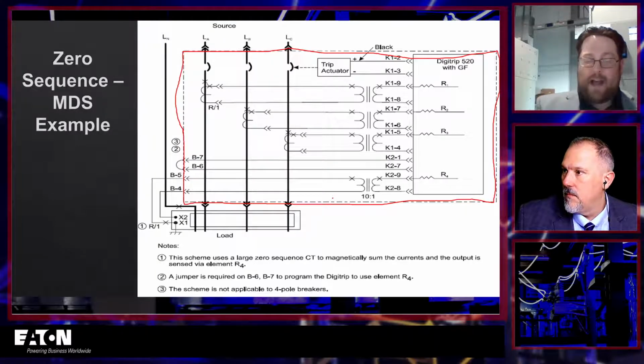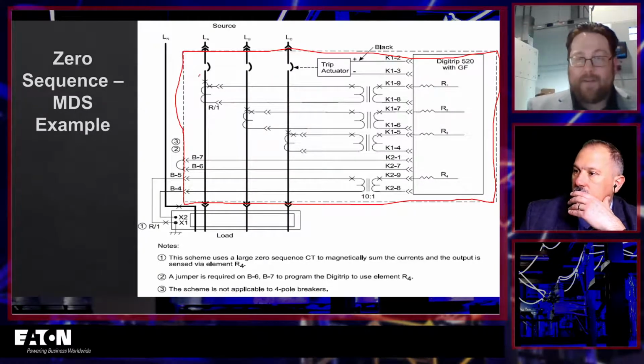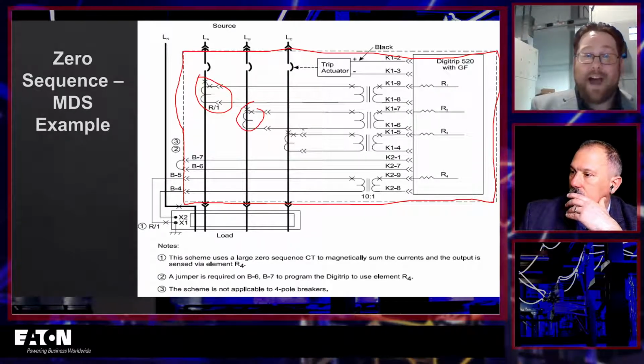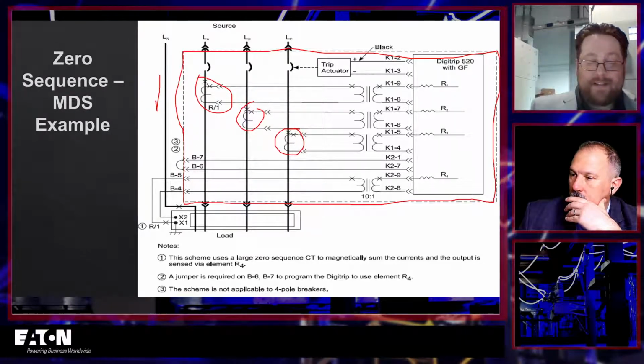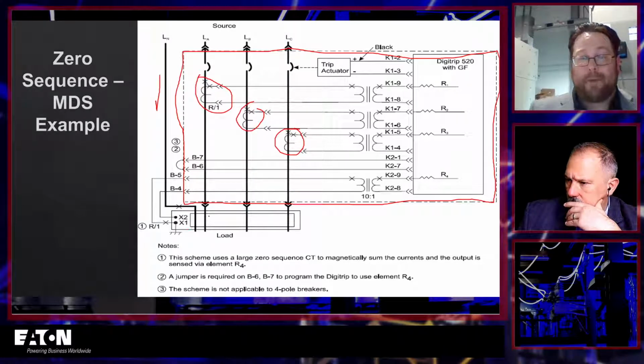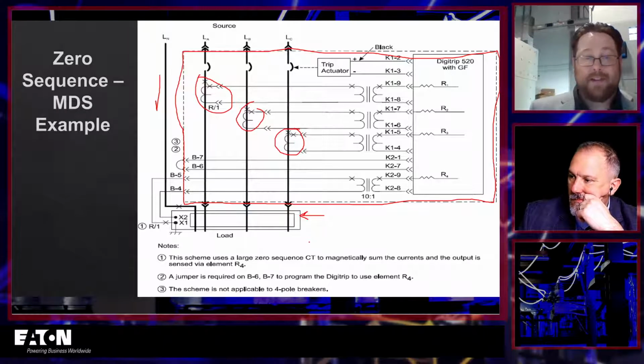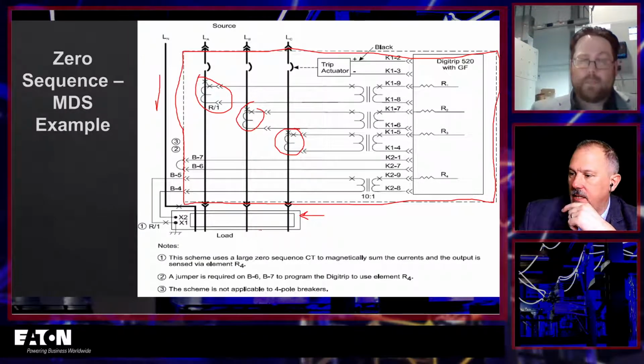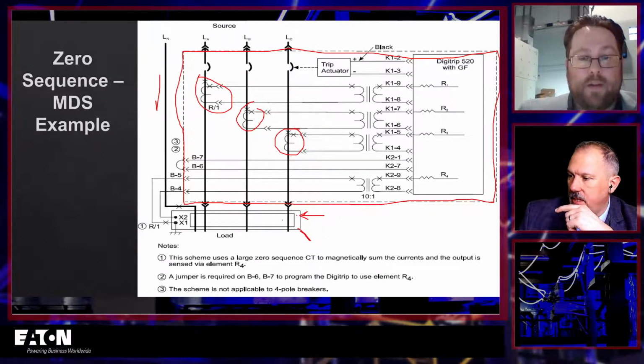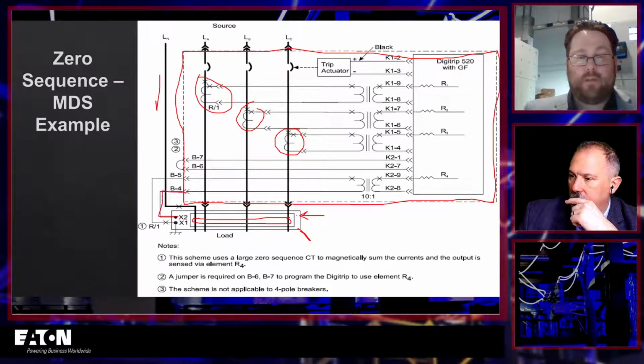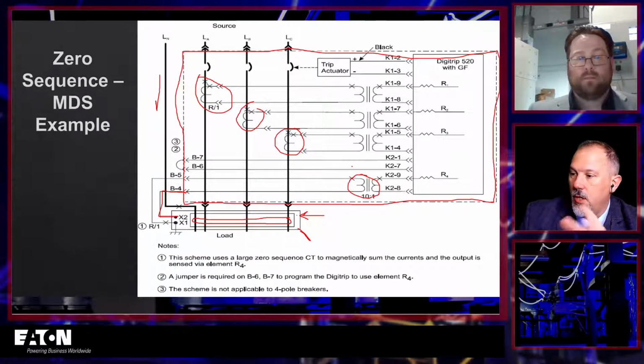So the circuit breaker has its CTs on the three-phase conductors. There's actually no CT now on the neutral conductor or that ground path, but we have that zero sequence CT at the bottom that's wrapped around the neutral and all three phases, like we saw in the diagram earlier. Okay. And that is again feeding into the trip unit. So you're saying that this down here is a zero sequence CT that's around these four conductors, right? And then the output of this goes into the circuit breaker trip unit, and there's another 10-to-1 ratio, so we're stepping it up again.